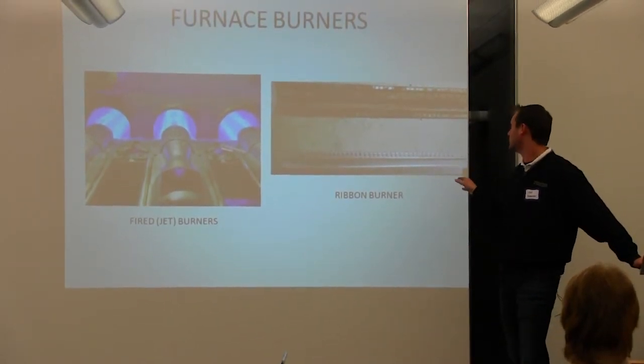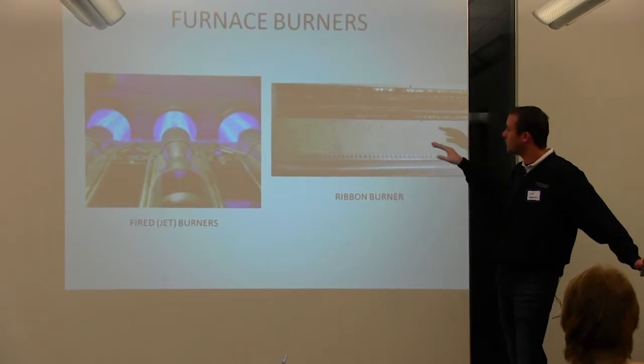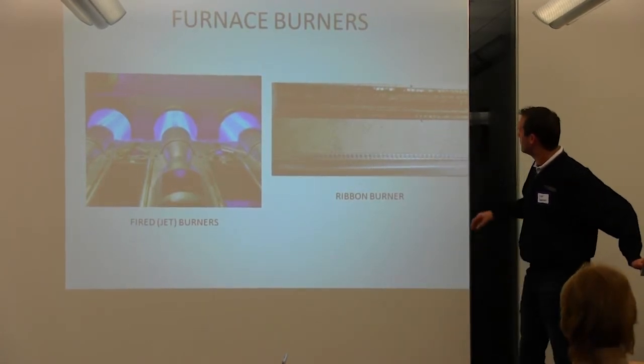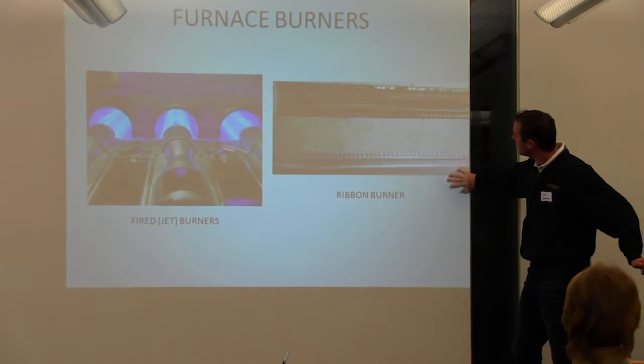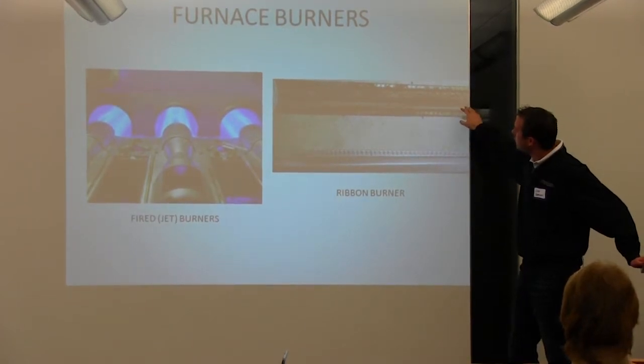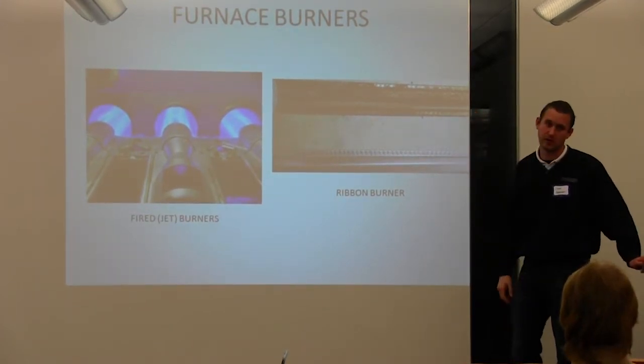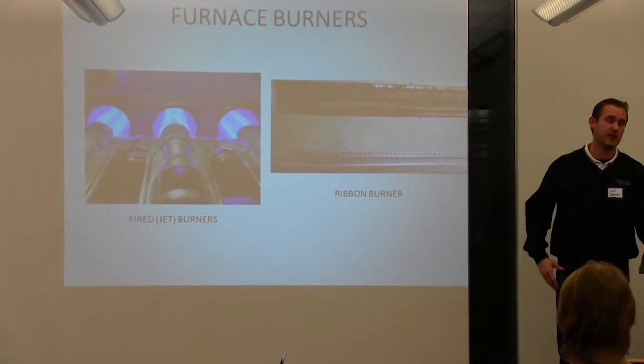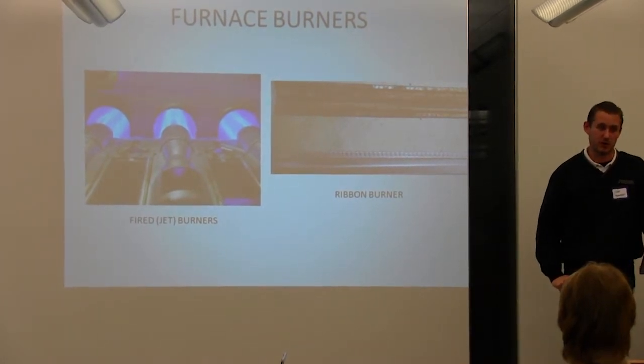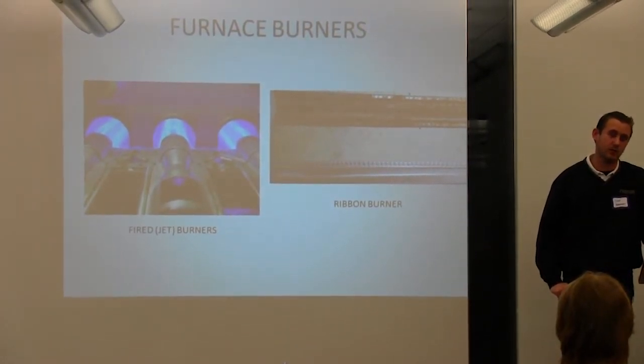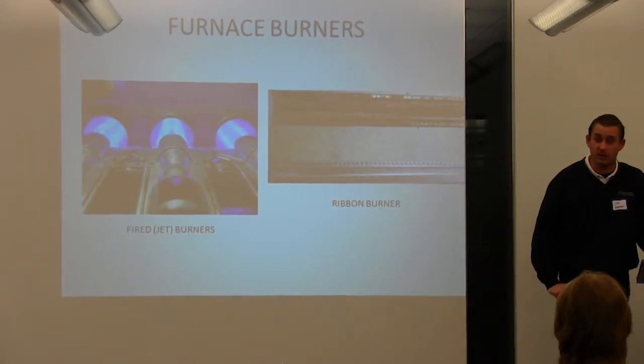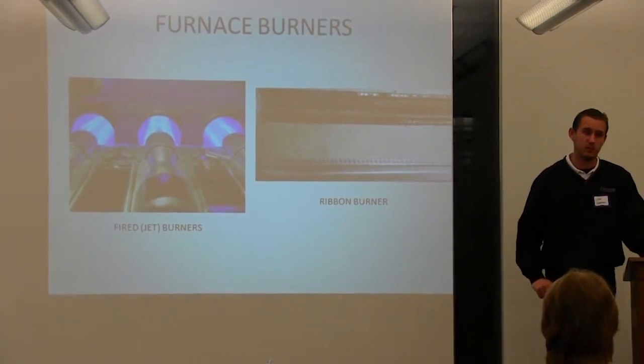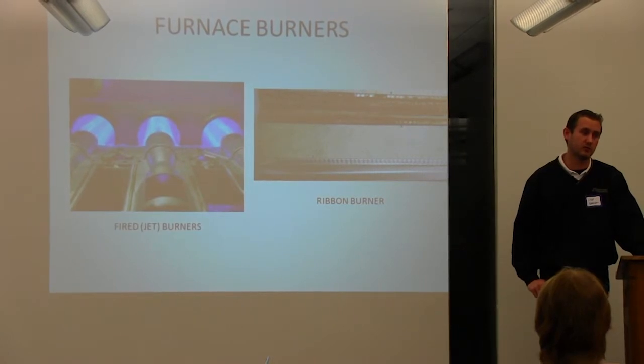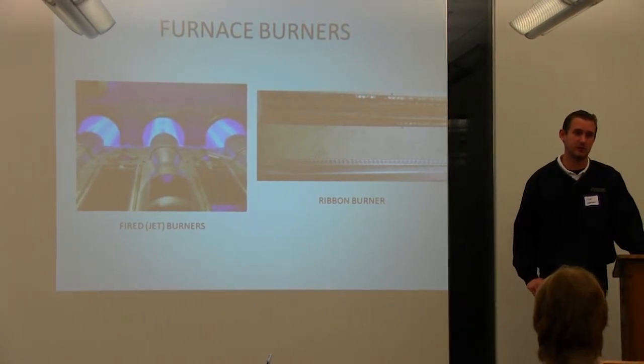The ribbon burners, on the other hand, have a tendency to corrode over time, and they can collect debris, and you can see the difference between a new one on the bottom and one pulled out on the top, and you can see how that corrosion starts taking place. And if you have a ribbon-style burner, it is very, very helpful to pull those out maybe every 5 years and just use a wire brush and really, really scrape those clean so that the gas can get through and combust efficiently.